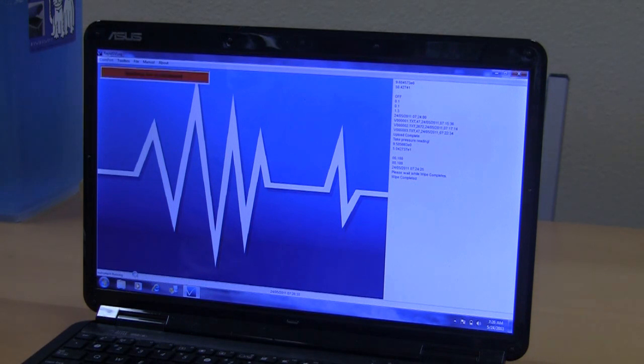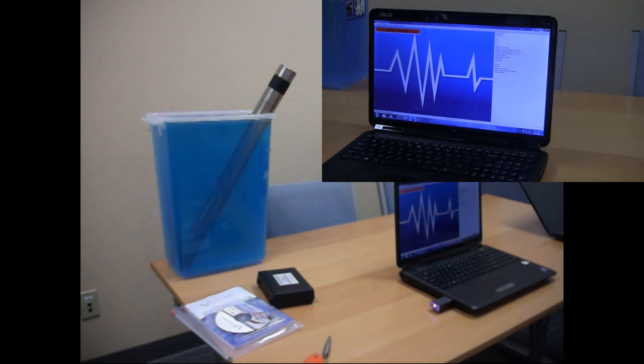So you really shouldn't be deploying the probe anywhere close to the end of the 2-minute period. So when the bar is yellow, you should really be waiting until it turns green again so you can make sure you get the probe out into the water before this interruption procedure starts occurring. So what's happening here is the RapidSV log is trying to establish a Bluetooth connection with the probe, and it can't do that because the probe is right now about 1,000 meters below the surface of the water. So it will continue to do this until the probe re-emerges. So this is not a problem at this point, the fact that the software here is trying to interrogate the probe. It will keep doing this until the probe comes back into range.